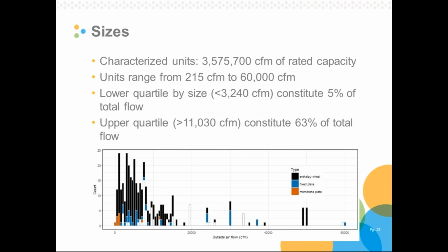Let's talk about size. We learned some really interesting things here. Of these units we characterized, there's about 3.6 million CFM of rated capacity. Units range over a huge range of size, 200 CFM to 60,000 CFM. What's really interesting, you can see in this chart, which is the count of units by type, wheel, fixed plate, membrane plate, as a function of outside air flow rate. The lower quartile, so the bottom 25% of units less than 3,200 CFM, constitute only 5% of the flow. Meanwhile, the upper quartile of units, so 25% of units greater than 11,000 CFM, constitute 63% of the total flow.